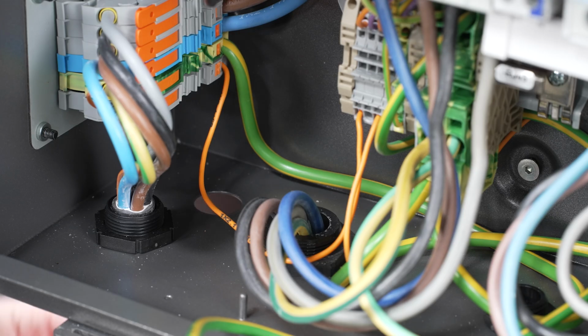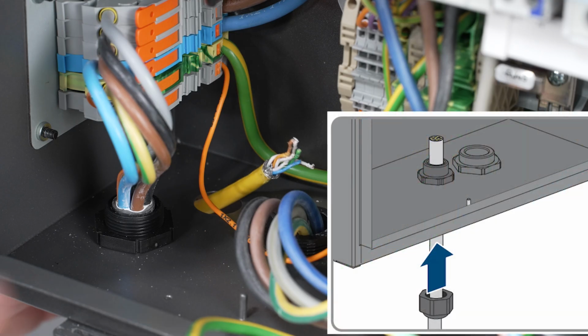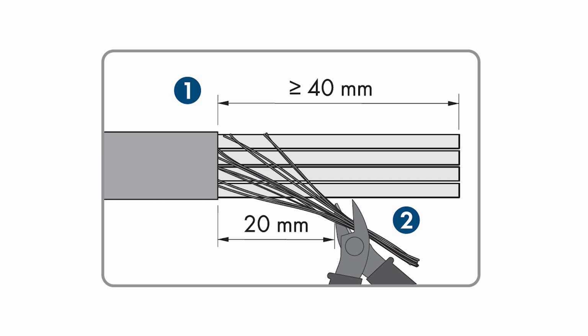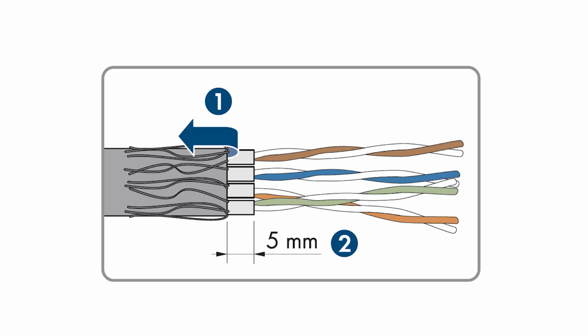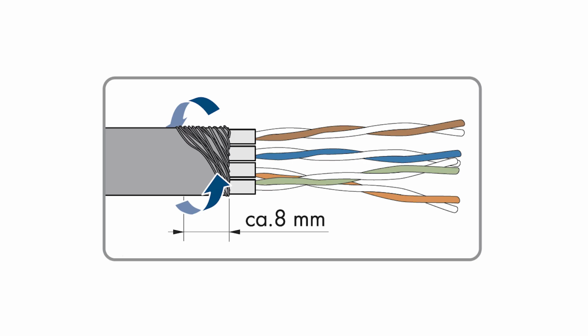Feed the network cable through the cable gland into the product. To do this, loosen the union nut, loosen M20, strip the network cable at least 40 millimeters, and shorten the braided shield to about 20 millimeters. Fold the braided shield back and trim the shielding to 5 millimeters. Evenly wrap the braided shield around the cable jacket to about 8 millimeters.